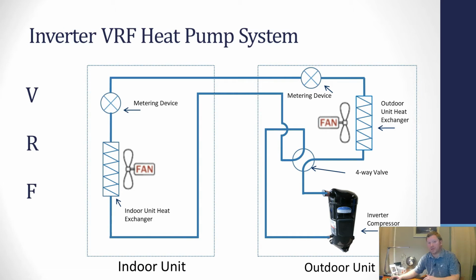Now, when we start looking at PID control, the VRF systems use a very similar control logic, but by having the expansion valve at the indoor unit, we can add additional PI controls, and that's really focusing on something called superheat and subcooling. And I'm only going to give you guys just a generic overview of this because it gets pretty deep pretty quickly, and we're going to be focusing on this way more with heat recovery systems. But basically in the heat mode, and I don't have this drawn up for heating or cooling, but just verbally to give you an example, that hot gas is going to go to that indoor unit heat exchanger, and what that electronic expansion valve's job is completely to do is control subcooling.